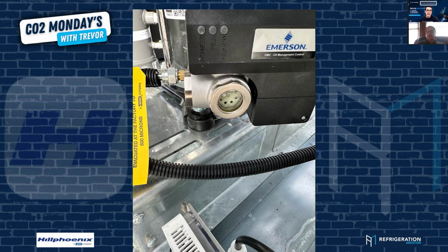Yeah, 100%. Totally agree. And that is your settings too, right? So this is where, when you're working on Hillphoenix Advansor, when you're working on somebody else, they could be running at 600 because it's a different design. They could be running air conditioning in that flash tank, right? Yep. Just remember, you got to understand the system you're working at hand, and no different for the other manufacturers. Don't just go and start changing the settings. There is a little minor tweaks, but that's what you work with the manufacturer on, because this is what the customer designed, with hopefully the manufacturer as well as the contractor involved. And that's where I think the best equipment is getting built, is when the manufacturer, the end user, and the contractor all work together and understand where it all is.